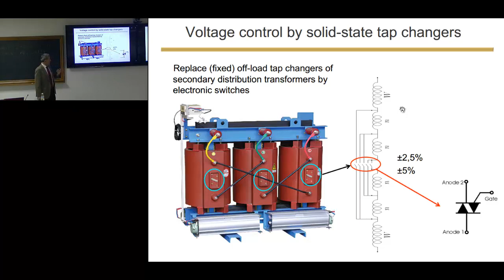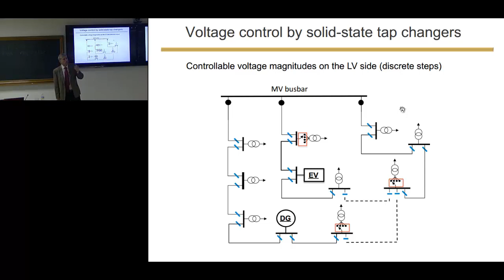Once you put the transformer in service, there is no way of moving it unless you disconnect the service and move it. So this is seldom done. This is seldom changed. If you replace the mechanical switch with thyristor switches, you can do it as many times as you want, as frequently as you want. So this gives you flexibility to regulate the voltages on the low voltage side. So, for instance, here, if there is a voltage problem, you can regulate the voltage so that the low voltage is screened from the medium voltage variation. So you can strategically locate tap changers in those places where you have voltage problems, okay?